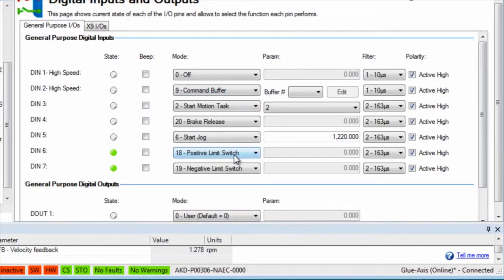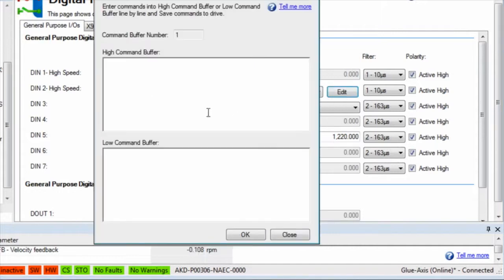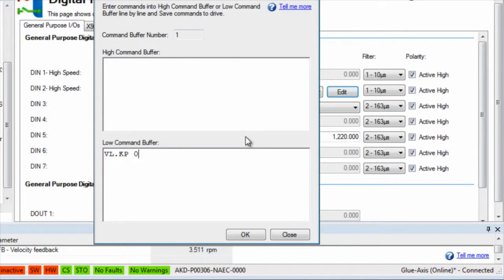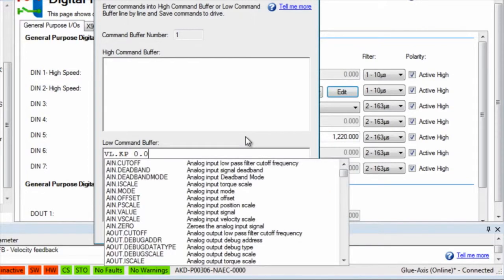Input 2 is set to mode 9, command buffer. There are 4 command buffers available and each has 2 states, a high and a low. A common use is to be able to adjust gains by an input.